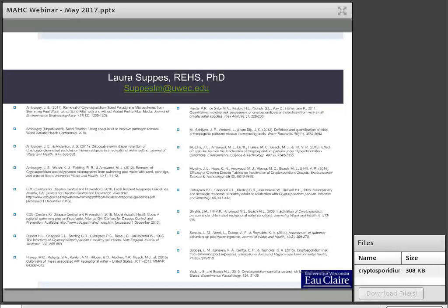The one that he has researched in his lab is polyaluminum chloride. I'm not sure specifically what brand names are associated with that, but that's one where he's seen sand filtration increase in efficacy with that coagulant added, with a lower filtration rate, and also with a deeper sand bed.